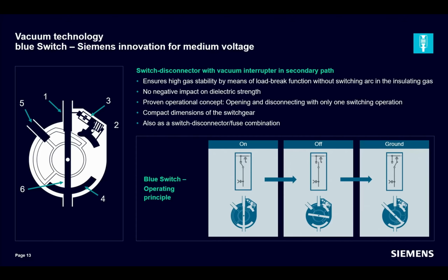On the first picture on the left-hand side, you will see the Blue Switch in a schematic diagram. Marked with number 1 is a busbar contact, which is connected with the busbar of the switchgear. On the right-hand side of the busbar contact, marked with the number 2, is a sliding contact, or so-called auxiliary contact. These two contacts form the so-called auxiliary path to which a vacuum interrupter is attached, marked with the number 3. The number 4 is the cable feeder contact and also part of the circuit of the switch. It transmits the current to the switchgear's cable feeder connectors. An earthing contact is marked with number 5, and it is connected to the ground busbar via the compartment housing.